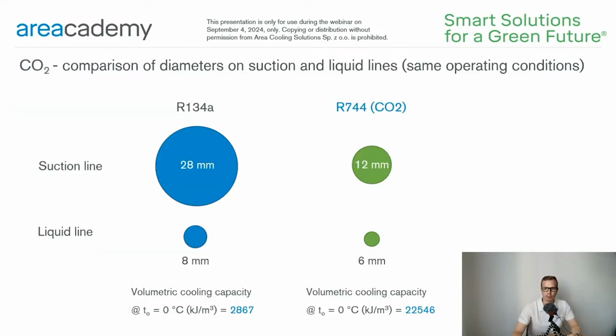Let's go back to pipelines for a moment. Here you can see a visualization of the pipeline cross-section for R134A and CO2. The CO2 is more dense and has significantly higher volumetric cooling capacity. That's why the pipeline diameter for this refrigerant can be much smaller.